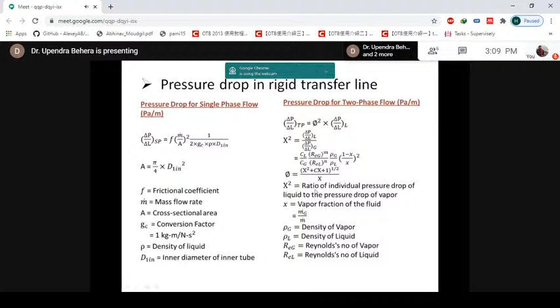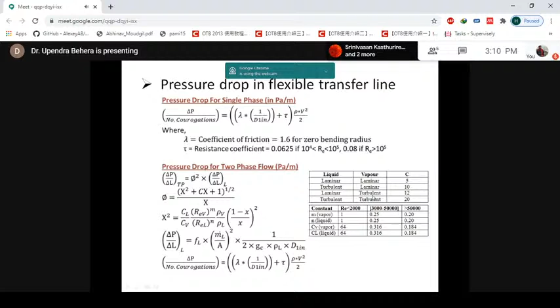The pressure drop in a flexible transport line is different from that for a rigid transport line, and this is for the flexible transport line. This equation we have taken from Witzenmann, the corrugated bellow manual. This is the correlation given, and we have used it for calculating both two phase and single phase pressure drop in our flexible transport line. Here are some parameters given in this correlation, the different constants m and n, and for liquid and gaseous conditions C_L and C_G; all that is available in the referred textbooks for design of cryogenic transport lines or vessels.